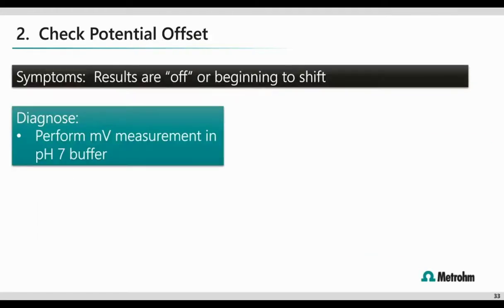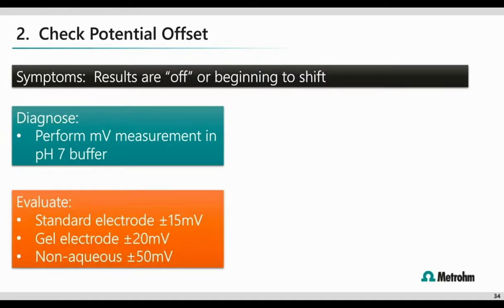Number 2, check the potential offset. If you're experiencing results that are off, whether they're higher or lower than normal, or they're beginning to shift, consider testing your electrode's potential offset. This is the difference between what your electrode is measuring versus the ideal millivolt reading of a buffer. First, perform the millivolt measure of pH 7 buffer. Next, evaluate. Is your measurement within the offset limits? Depending on the type of electrode you're working with, you may have different offset limits.